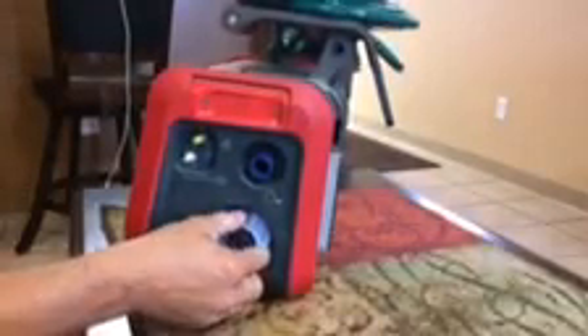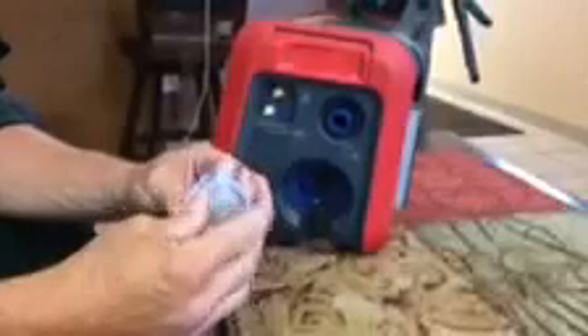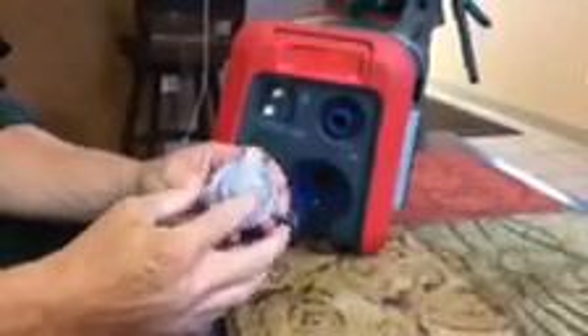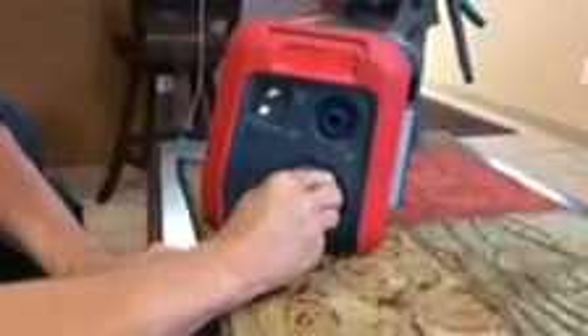What's unique about this ventilator and the exhalation port is that this will actually pop out. And these are disposable. However, they can be reused, and I would encourage you not to just throw these out if you don't have to. Why you would have to get rid of these is if the diaphragm was damaged. What this diaphragm does is it seats over this valve and basically that's what's going to maintain your PEEP. That's what's going to maintain your pressures on your ventilator. It locks in here like so, and it goes in one way. You're going to turn it to the right, you're going to feel it snap in place, and it'll go nice and tight.